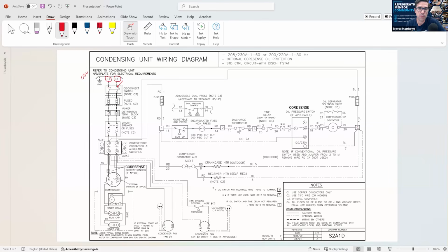We put it on L1 now. It should say, for example, 230 volts. From there we can go down to the next one right here, 230 volts. So we're going down to the fuses: on the upstream side of the fuse, 230. Downstream, which is the next stuff, we check, oh, I got 230 there. Great. Now we keep going through, and you start writing all this down on your electrical wiring diagram.